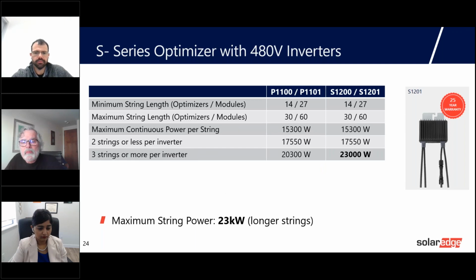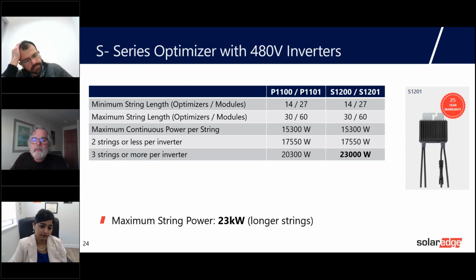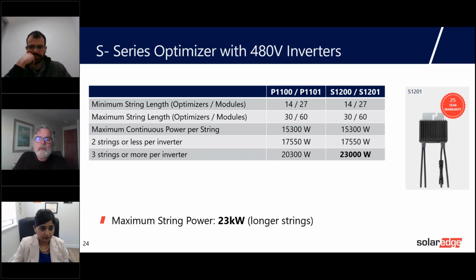So same type of information. This is for our 480 volt three phase inverters. We operate the fixed DC voltage here much higher than we do at 208. So we're at 850 volts. So all of the minimum string lengths and maximum string lengths increase due to the fact that we have much higher DC voltage at the inverter input level.